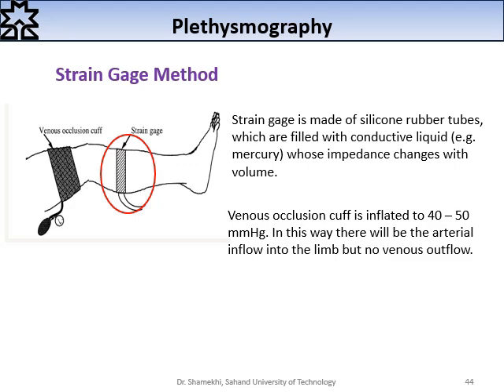As I told you in the previous slide, plethysmography in general is a method to record the changes in the volume of an organ. Therefore, we should use methods to measure the change in our organ, and the first method is strain gauge based plethysmography. A strain gauge in this type of plethysmography is made of silicone rubber tubes which are filled with conductive liquid whose impedance changes with volume.